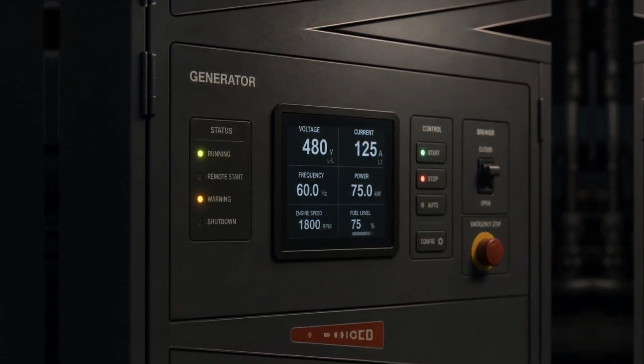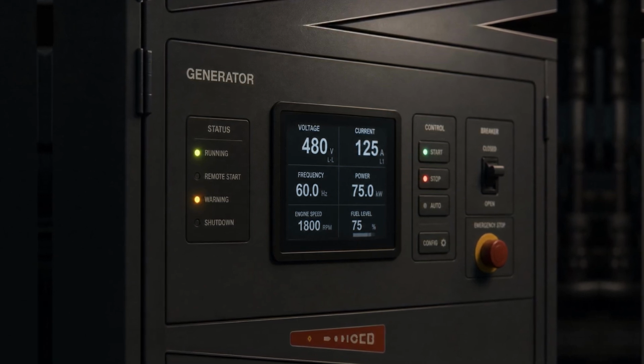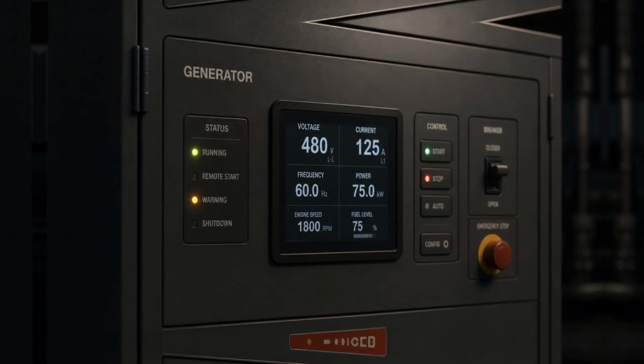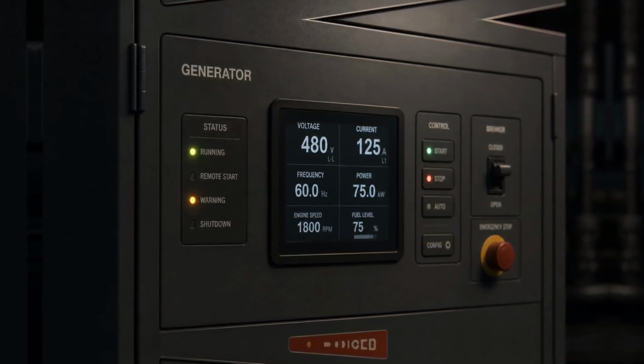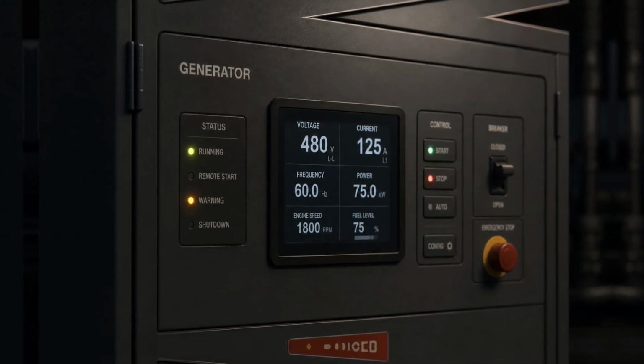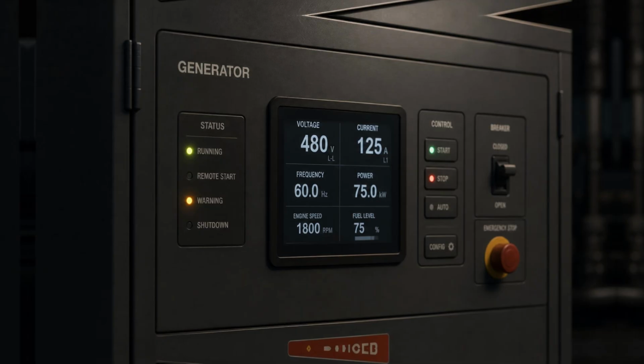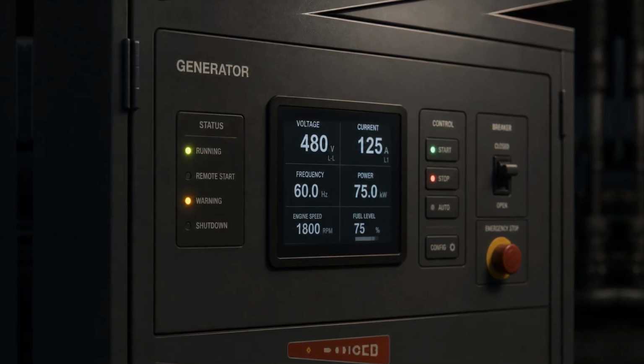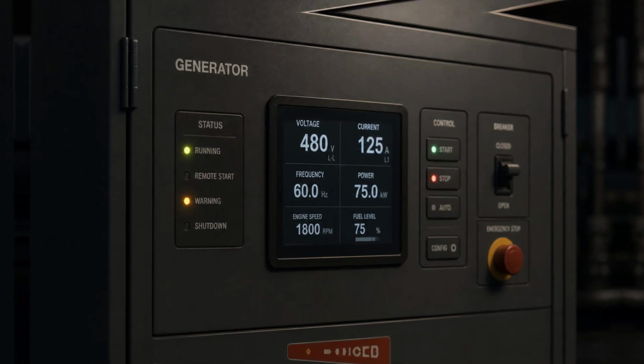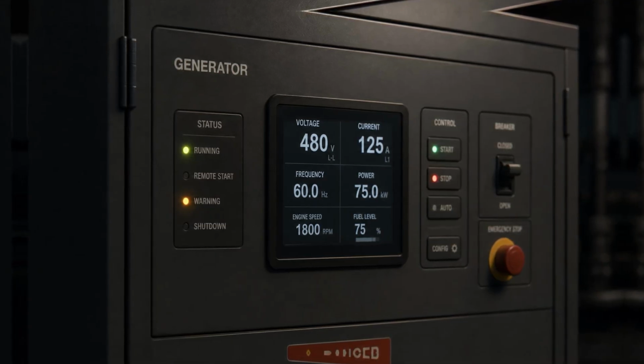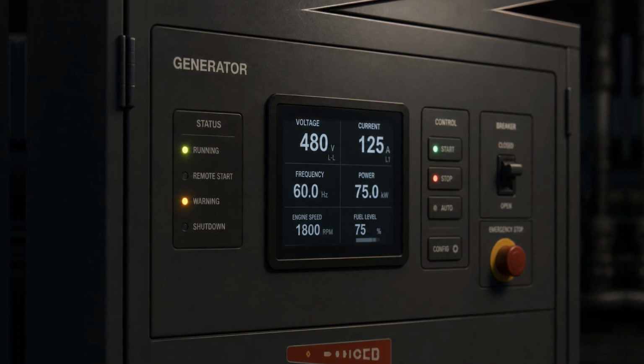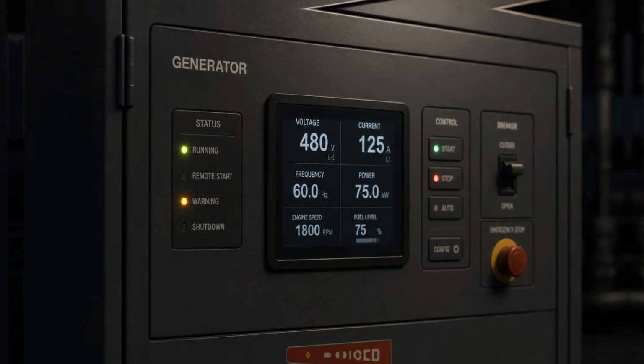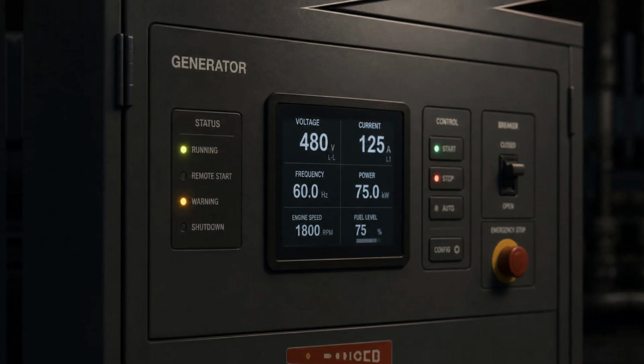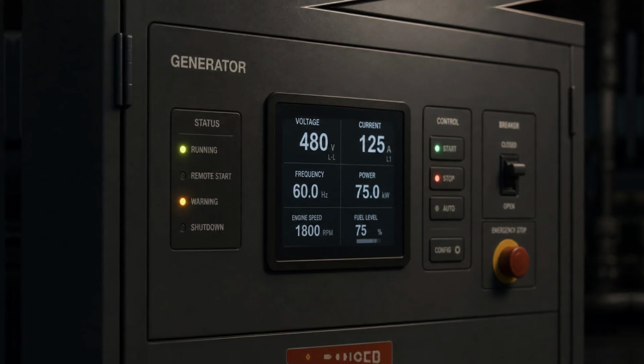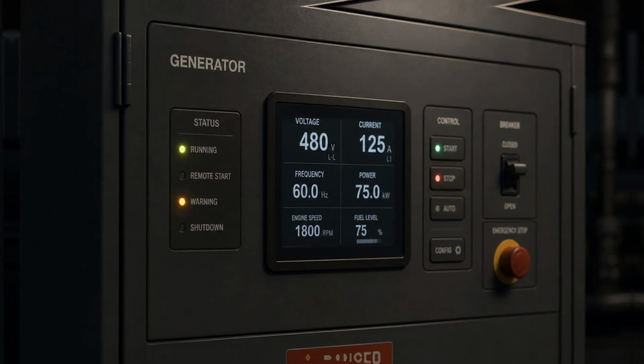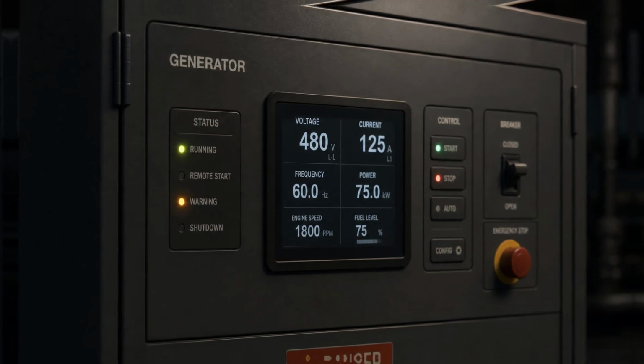At the heart of any UPS is a bank of batteries. These are not the small batteries of consumer devices, not the kind that fit in a drawer or power a remote control. They are purpose-built cells, often lead-acid or lithium-based depending on the application, arranged in strings and cabinets and enclosures designed specifically for the job of storing electrical energy in quantity. In a large commercial or hospital UPS installation, the battery cabinets may fill an entire section of an electrical room or occupy a dedicated space of their own. They are heavy, they are carefully ventilated, and they are, at every moment during normal operation, in the process of being kept fully charged and ready.